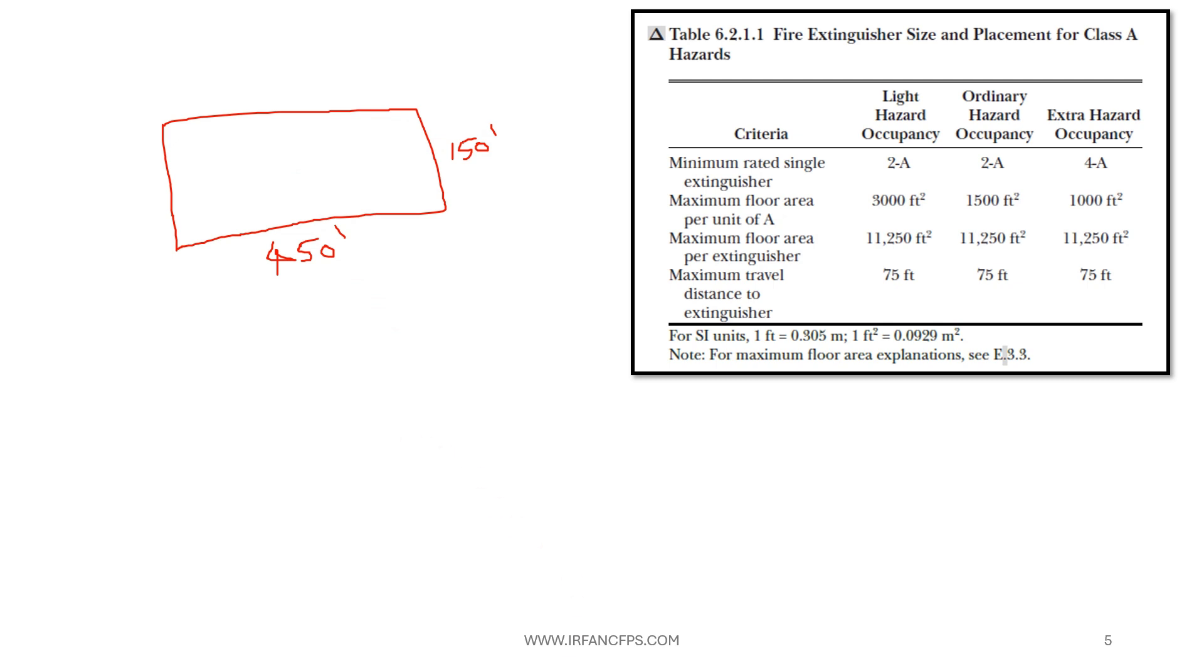So as per the table, the maximum floor area per extinguisher for any hazard will be 11,250 square feet. So our building area we need to calculate. So our building area will be 450 feet multiplied by 150 feet which will be equivalent to or which is equal to 67,500 square feet. So now we got the total area for our building.